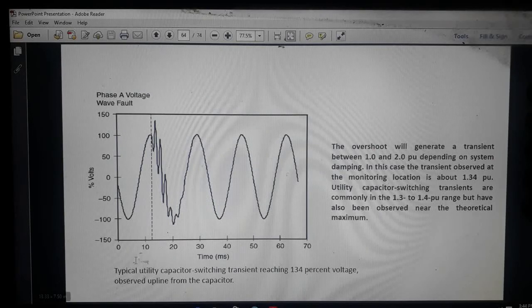Now here, the time is in milliseconds and the voltage is in percentage: -150, -100, -50, 0, 50, 100, 150. You can see this waveform of our voltage. This is the negative maximum amplitude of the voltage and this is the positive maximum amplitude of the voltage. Here, for a minimum time period the amplitude exceeds the maximum positive amplitude of the voltage, which generates a transient over voltage.